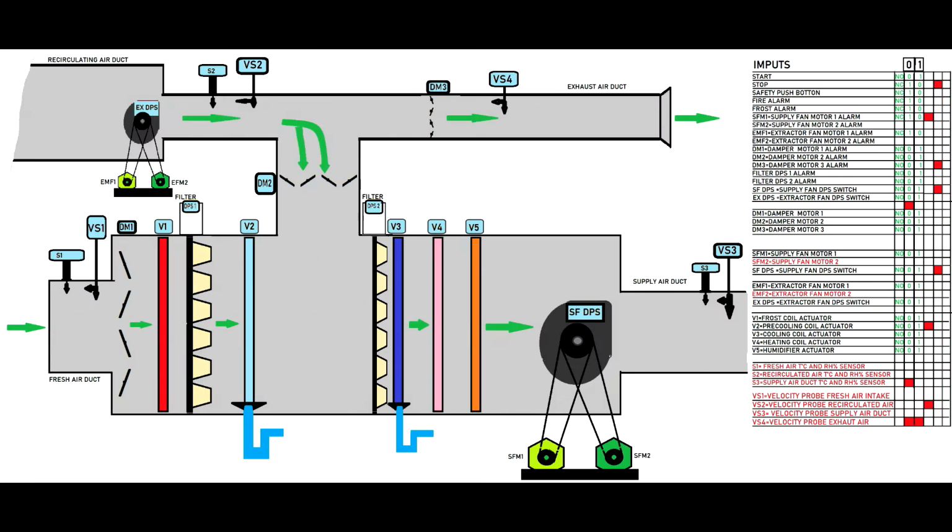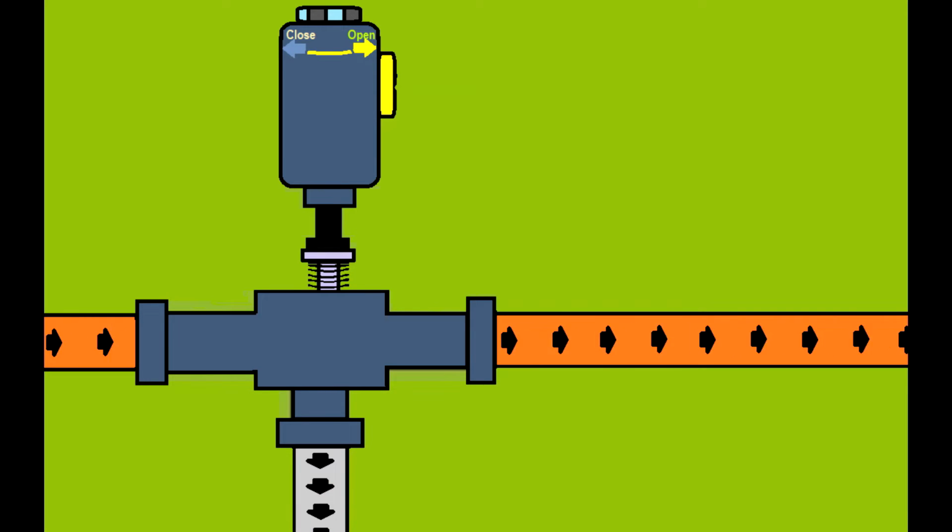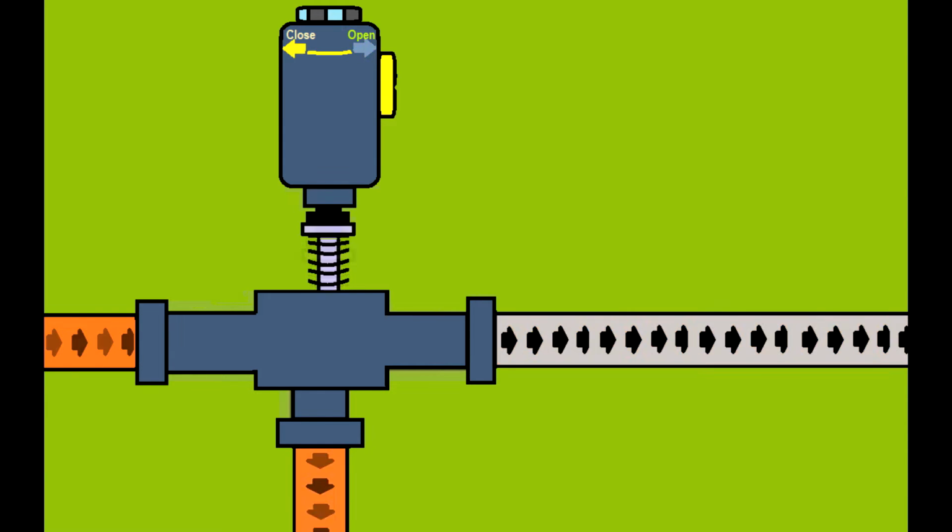Like I said, an HVAC engineer will write the control philosophy and the software engineer will apply this onto the PLC, and then the PLC will control the air handling unit accordingly. It will control the fan speed, and it will control the heating and the cooling heat exchanger. Even the chiller can be controlled by the same programmable logic control. The heating and cooling or the dehumidification process will be controlled by actuators, which will allow the heating or cooling agent to pass to the heat exchanger.